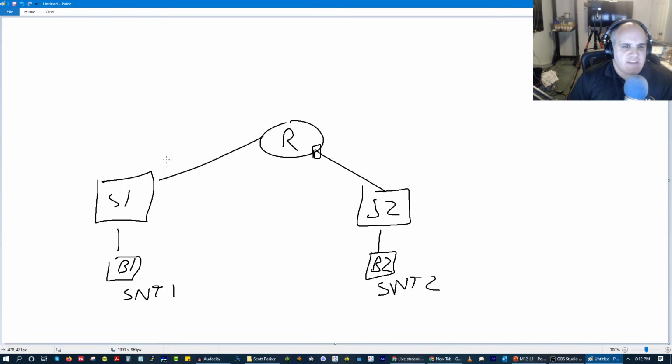And the reason why is, imagine I initiate a broadcast on subnet 1, and it's able to be forwarded to subnet 2, subnet 3, subnet 4. It crosses these subnet boundaries. Before you know it, everyone in the world who's on the internet is sending broadcast messages all over the world and totally overwhelming networks. That's why we have broadcast boundaries, and we cannot send broadcasts outside of our subnet. Okay, so our broadcast cannot leave our subnet. Now with BACnet, that's not necessarily true, and we'll talk about that.